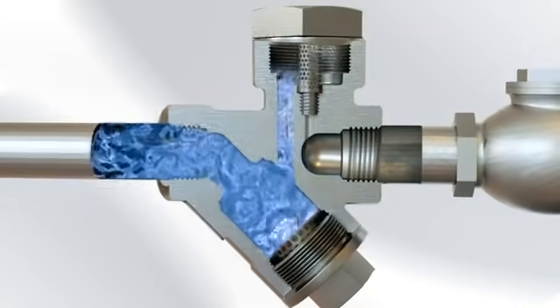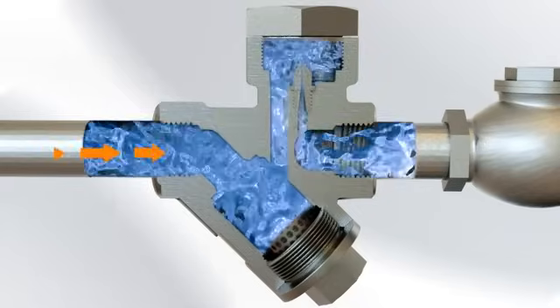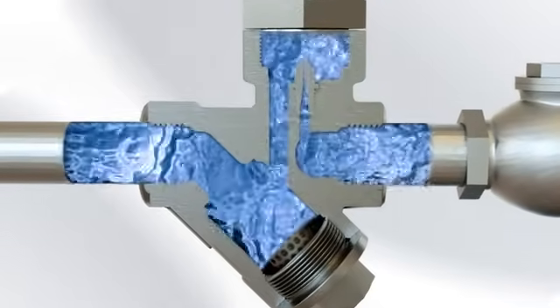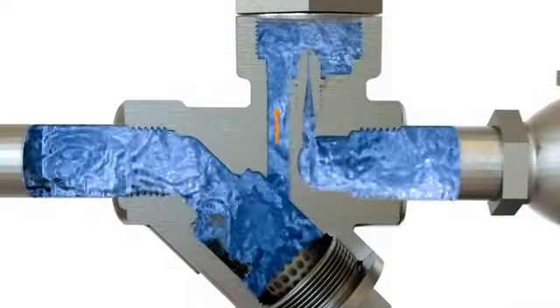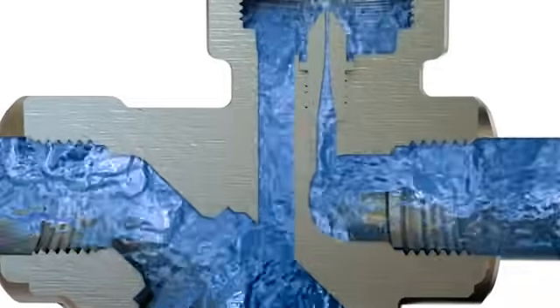At startup, the water is at very low pressure and temperature, so no flashing occurs as it exits the Venturi. This means there is no back pressure present to restrict the flow of cold condensate as it exits the Delta Trap.